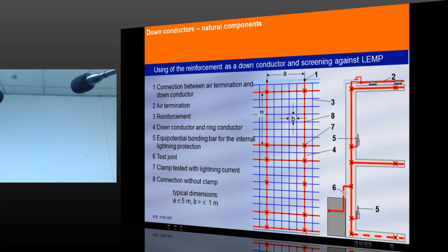I hope you understood. So you can use the steel reinforcement, provided you take care of the connection between the steel inside the concrete and an outside object, because of corrosion. The second point is with respect to strength. Every 5 meters you need to have a clamp or a welded joint which is tested to withstand partial lightning current. And every 1 meter you can have a normal connection.